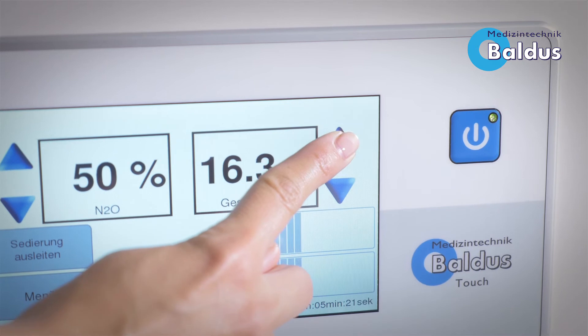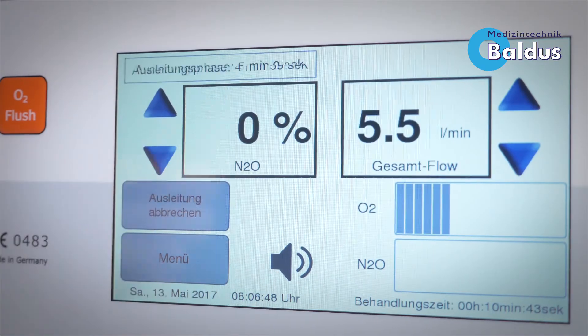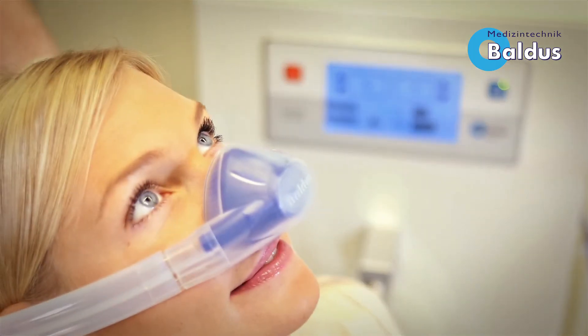We have made it safer for the clinical team by increasing the maximum flow to 18 liters per minute, which is also a better sedation for the patient. The breathing bag will always be filled sufficiently, especially for patients with anxiety problems or patients with a bigger lung volume. The recovery button is pushed at the end of all sedation treatment, which will produce a flow of 100% oxygen and a countdown will start.